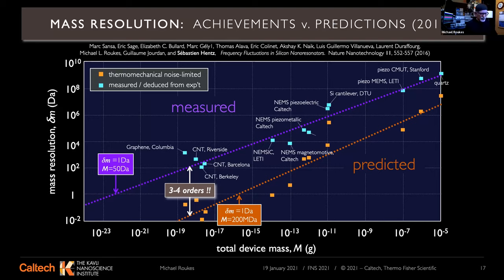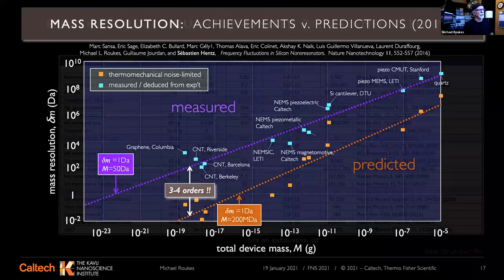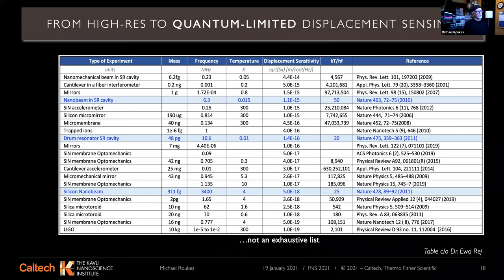Although we've pushed it down now in my group using piezoresistive sensing to about 5 kilodaltons, maybe a little bit lower. The main problem is that you can't get the devices cold, because piezoresistive sensing requires that input current—you can't take them down to low temperatures. We find that our devices hang up at around 50 Kelvin.